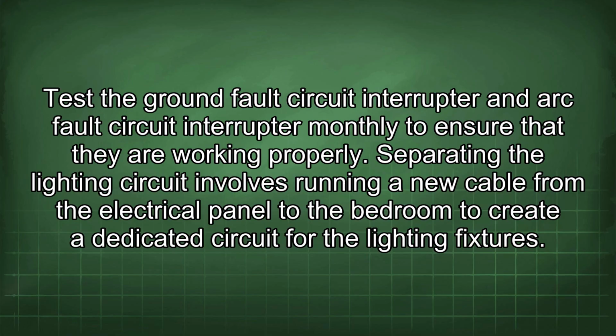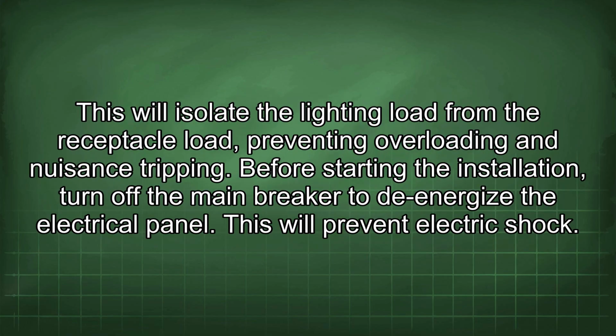Separating the lighting circuit involves running a new cable from the electrical panel to the bedroom to create a dedicated circuit for the lighting fixtures. This will isolate the lighting load from the receptacle load, preventing overloading and nuisance tripping. Before starting the installation, turn off the main breaker to de-energize the electrical panel. This will prevent electric shock.